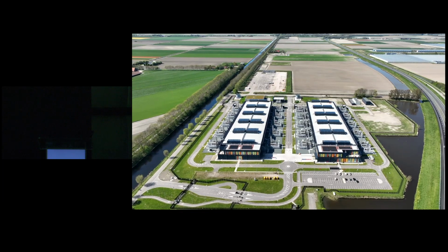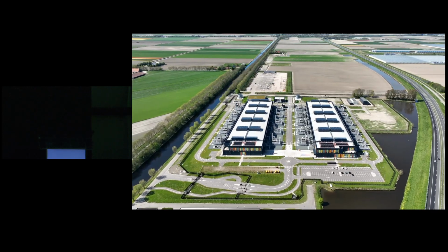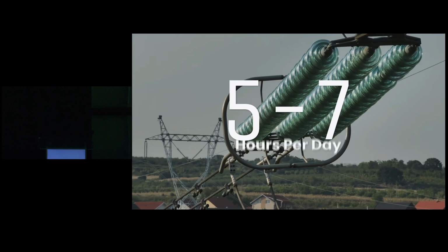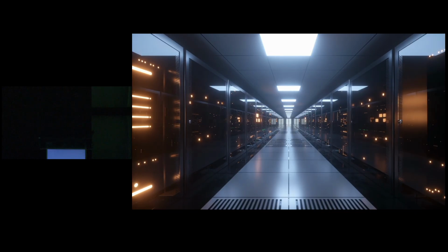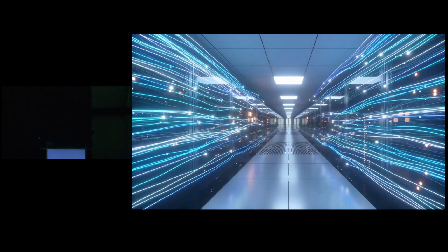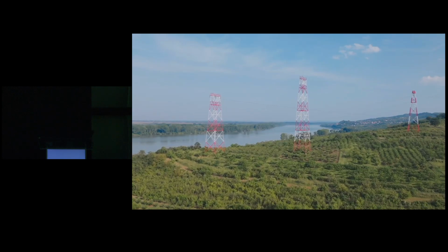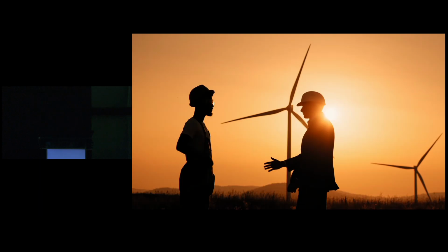It actually solves all the problems in one solution. What we've come up with is the ability to curtail 100% of the load with zero sacrifice, because you can take the data center 100% off the grid for 5 to 7 hours a day, every day. Now the data center is truly an asset to the grid instead of a liability. When you go tell a local utility that you're going to take a gigawatt scale data center and turn it into a responsive load, you're going to the top of the deck.